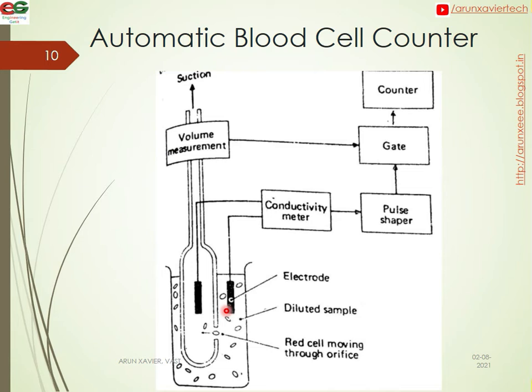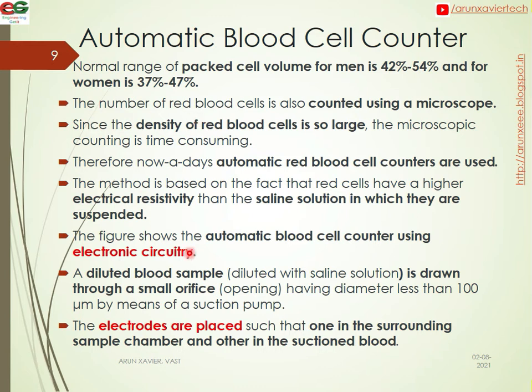We use a conductivity measure — specifically a resistivity change — to count blood cells automatically using two electrodes and a suction system. The diluted blood sample is drawn through a small orifice having a diameter of less than 100 micrometers by means of a suction pump.